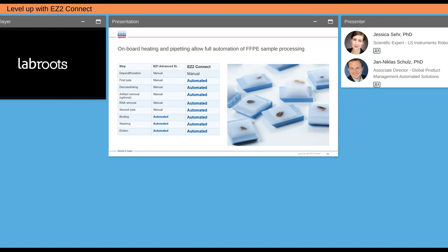But now with the EZ2, we have the option to automate the full process, which means after deparaffinization, we have a lysis step and a decrosslinking step, which is very important to remove the fixation-caused crosslinks, and then we can do the UNG step, so this optional artifact removal step, which can also be automated. Then we have an RNA removal step and a second lysis step, which optimizes the performance and increases the yield. All of these steps can be automated on the EZ2 Connect.